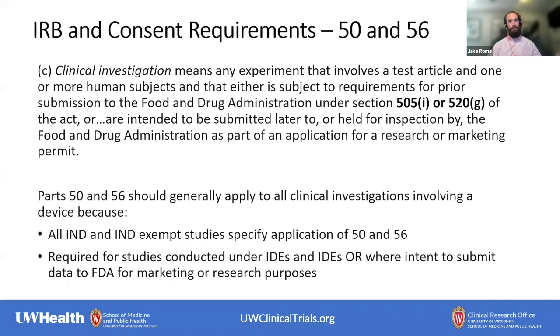As I mentioned before, the FDA likes to use different definitions. The definition of clinical investigation under parts 50 and 56 is slightly different than it is for the IND and the IDE. Basically, if you're planning to do a study and intend to use the data from that study to submit something to the FDA, or hold it in case the FDA wants to see it, then you're going to need to apply 50 and 56.